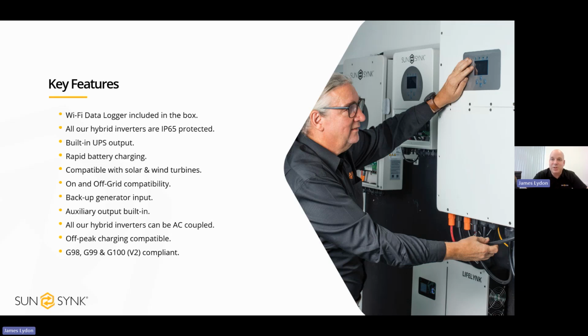So if the system is exporting 1.5 kilowatt, what it will automatically do is use the 1.5 kilowatt excess PV, but take the other 1.5 kilowatt from the batteries to give the immersion what it wants, to give it the full 3 kilowatt. And the diverter output control is based on battery SOC. So you might say, okay, only turn that divert on when the battery is at 100%, but turn it off when it's at 97%, 96%. Immersions will take bits of power, but in terms of efficiency, they're most happy when they get the correct power.